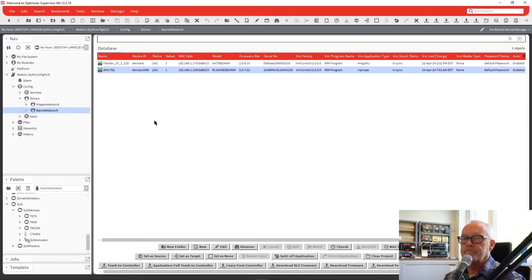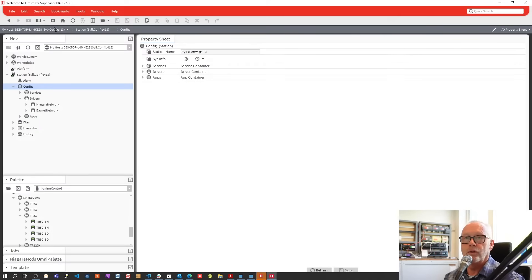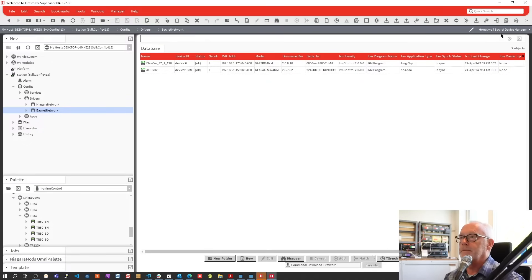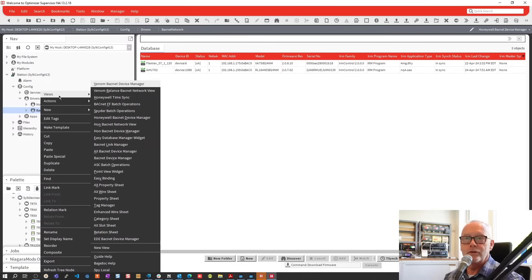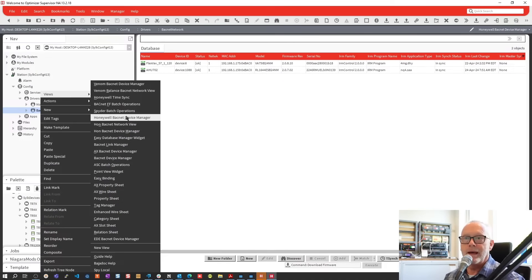This is the previous version before 4.13 came out. In the 4.13.2 view, when you click on the BACnet network, the default view changes from that HON view — there's now a new Honeywell BACnet device manager view. If we look at the different views available, there are quite a few device manager views. Honeywell has changed from the IRM BACnet device manager view to the Honeywell BACnet device manager.